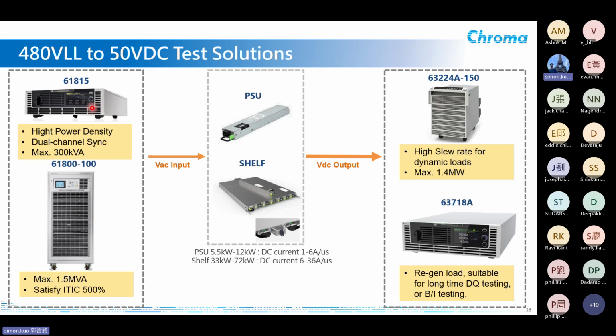If your customer wants to test at a mega level, you need like 10 pieces of the 61800-100, so the weight will be huge. So in some cases, we will recommend the customer use the 61815 because of this high power density, and the maximum we can reach is 20 pieces in parallel, which reaches 300K. That will satisfy most of the shelf testing requirements.